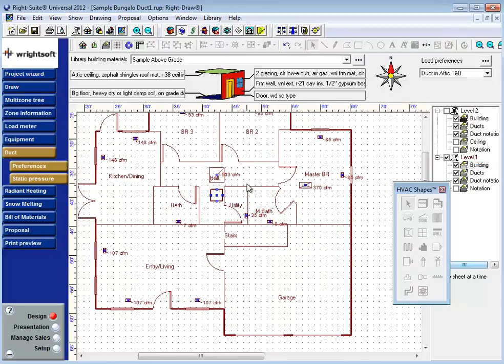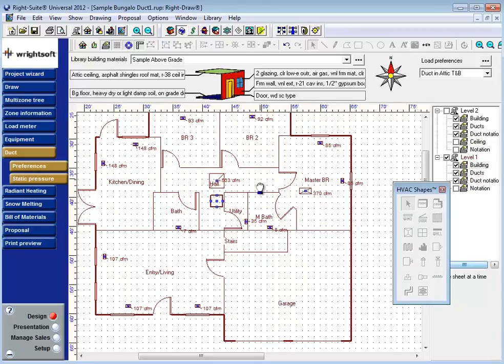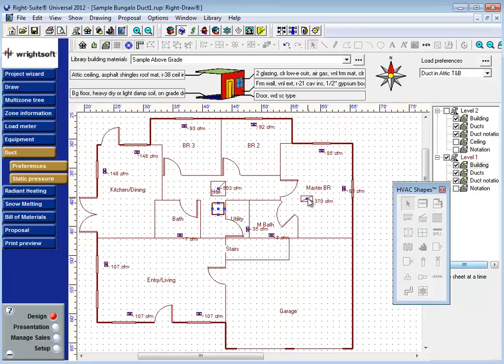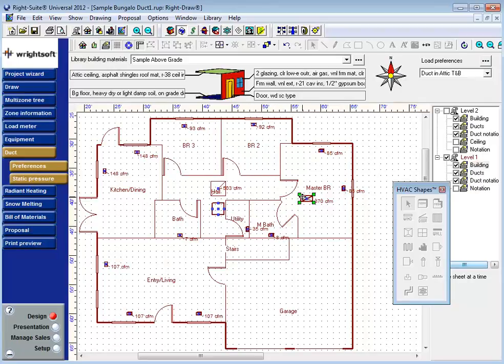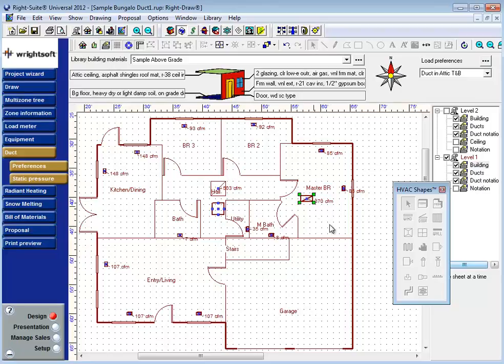If there are multiple return grills on a given floor, Wrightsoft will try to keep the air local using the registers nearby. However, Wrightsoft also wants to keep the air balanced, so it may find registers further away to assign to that return grill in order to keep the return grills relatively the same size.